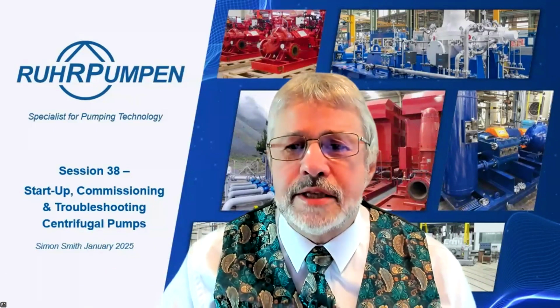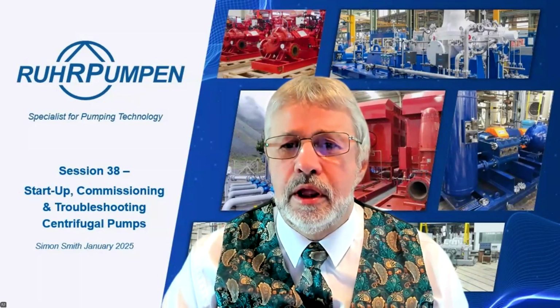Faiz ul Islam says, how does instrument air contribute to low flow? I wasn't referring, I think, in the presentation to instrument air, but if air should get into the suction pipework, it would contribute to low flow. Slugs of air aren't going to help it. I may have misunderstood, or I may have not explained very well what I meant.